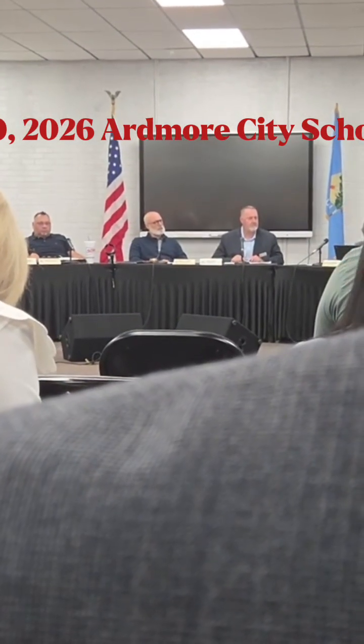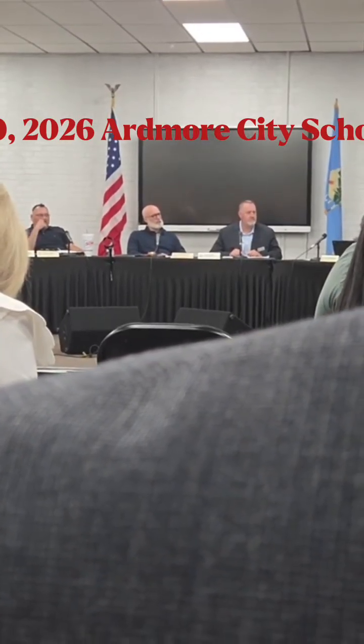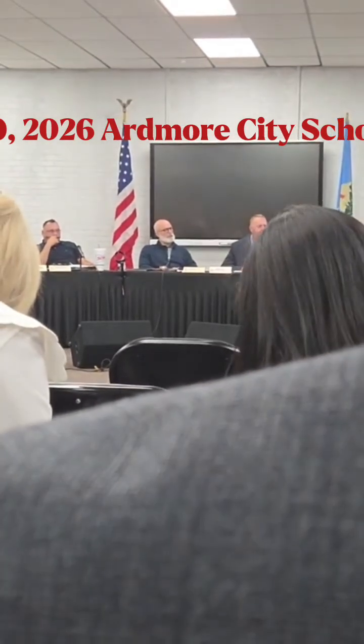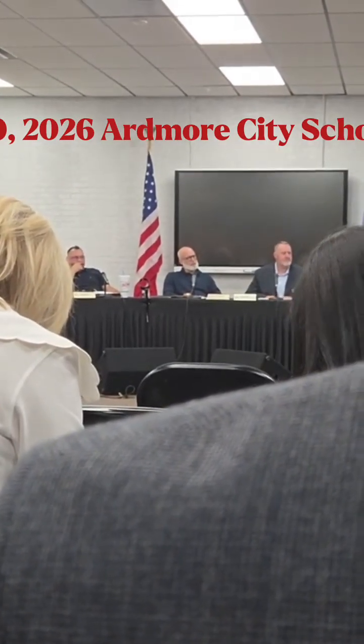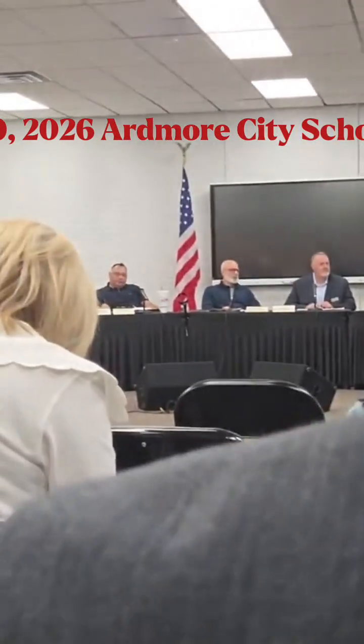So there are some options, depending on whether repair is viable. The heat pumps were manufactured in 2005. In 2010, BOMA published a preventive maintenance document, based on research, saying that at that time water source heat pumps had a life expectancy of 18 years. So these units are at 21 years against an expected life range of about 18. Newer units have improved manufacturing and technology, so you can get a bit more time out of them — probably up to 20 to 22 years. These are indoors, which helps protect them from the elements; they're not susceptible to hailstorms, high winds, or anything like that.